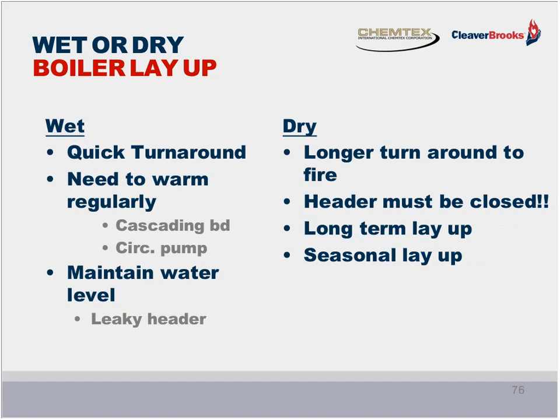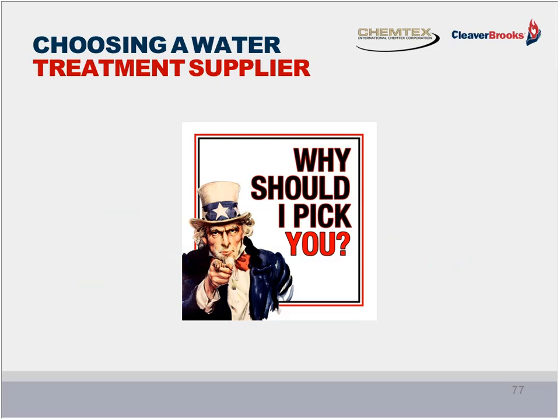And you need to maintain the water level while you're doing it, because oftentimes there's leaky headers on steam headers which cause condensate to collect in the boiler, causing dilution of your oxygen scavenger and alkalinity builder. And when it comes to boiler layup that's dry, it takes a little bit longer to fire the boiler up. It also demands that your steam header must be closed because you don't want water dripping back into the boiler. And this is recommended for longer-term layup, 2 months or longer, or seasonal layup where the system is down for the wintertime.